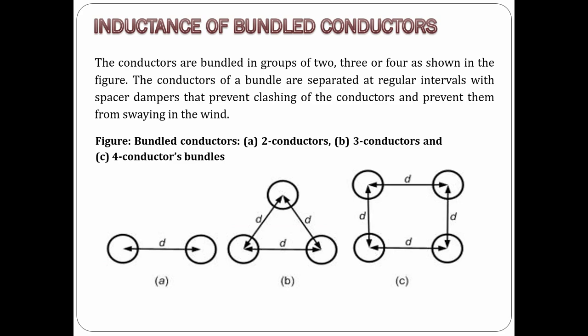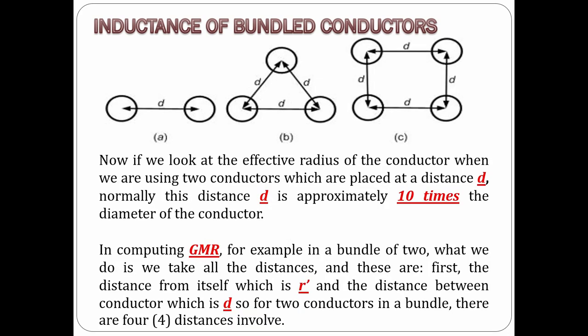We have two, three, and four bundled conductors, wherein the bundles are separated by spacer dampers to prevent clashing of the conductors. For example, in the two bundled conductors with distance d between conductors, experts say the normal distance d is approximately 10 times the diameter of the conductors.